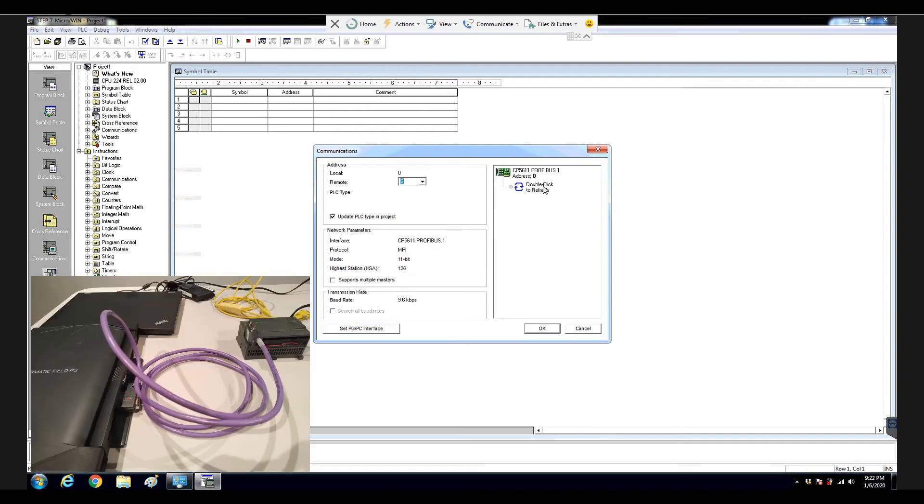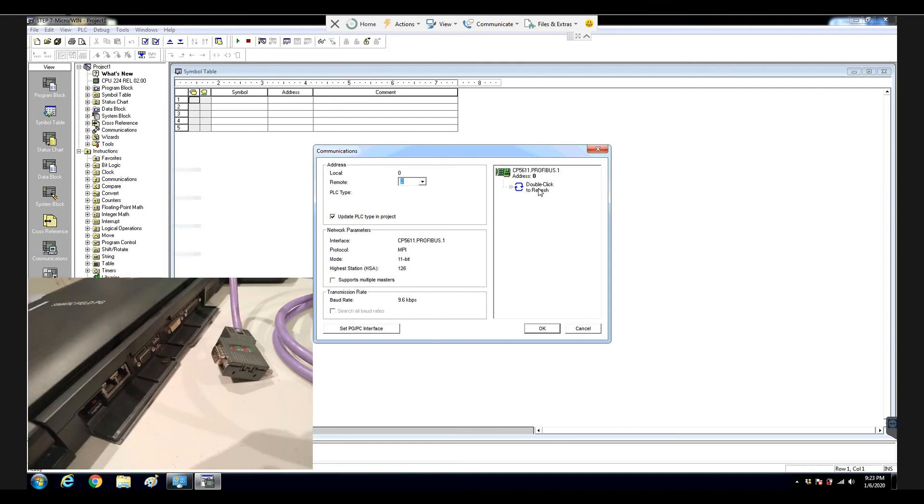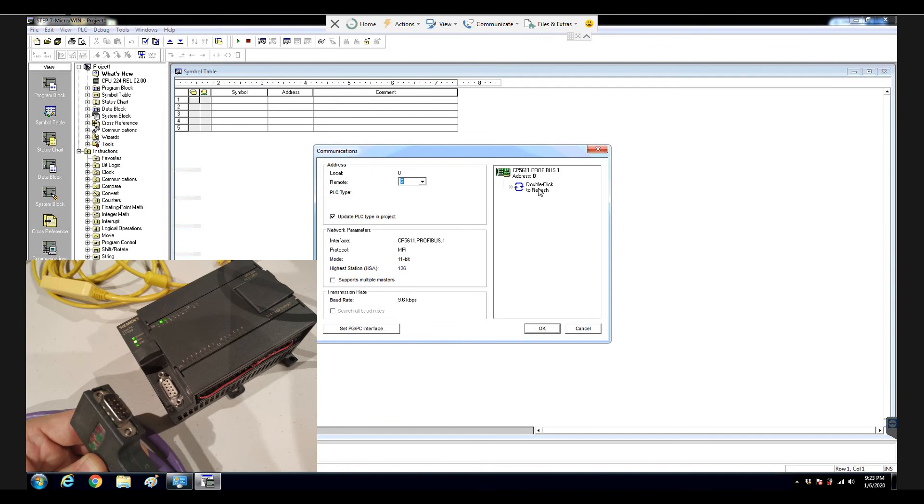The physical cable from the PGPC to Siemens S7-200 controller, that is the RS-485 cable. Usually, from Siemens side, they use the purple cable for that. Right, that cable, inside the cable, there are two cores, and behind this Siemens PG, there is one physical 9-pins RS-485 connector there. That is one female connector. The connector on the cable, that is a male connector.